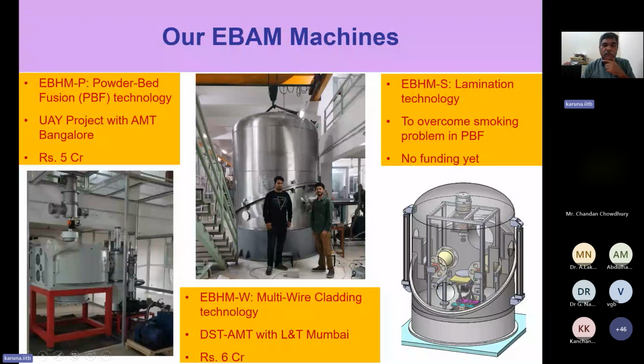But in spite of this kind of diameter, the wall thickness we use is only 8 millimeters, and we don't use any rib except one rib here and another rib inside the chamber. Only two ribs were used for strengthening because the hoop stress takes care of all these issues. Okay, so this was a very interesting thing. And in our machine, you will also see that the cut is slant. I'll come to that a little later. The cut is slant, and there's no separate door as in the first machine. We don't have any hinged door here. The entire thing, like an eggshell, will open and close.